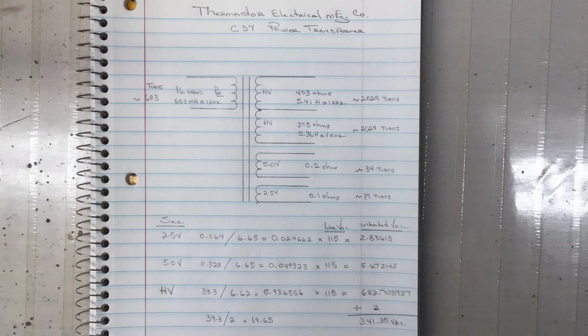Again, you can see the turns ratio is roughly 5.94, using my earlier method of inserting a signal from my signal generator, a sine wave at 60 Hertz, as compared to using the LCR meter, leveraging the magnitude phase and doing the math again with the transformer, looking at leakage inductance.